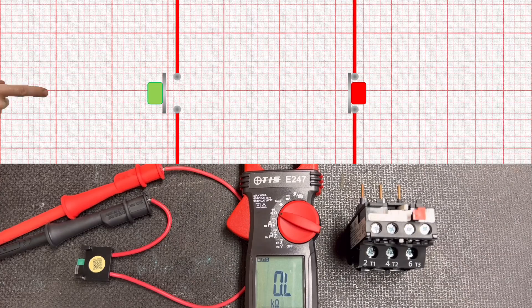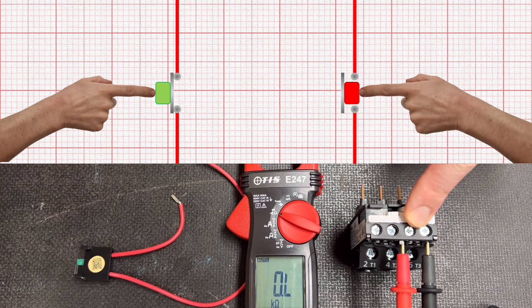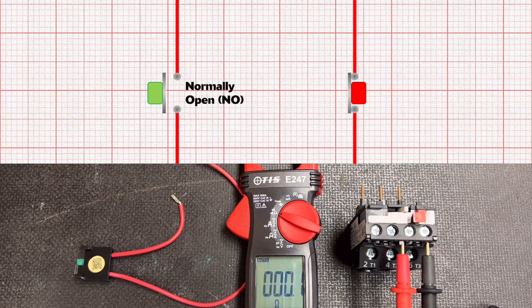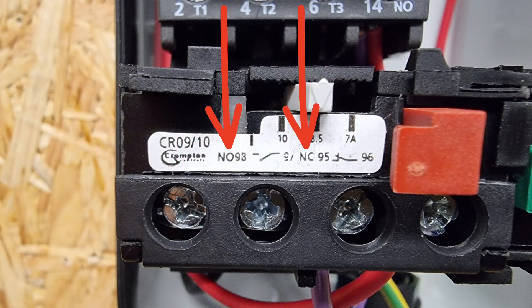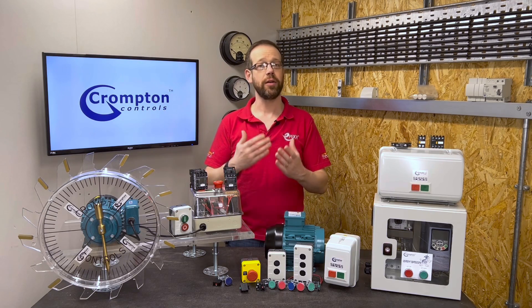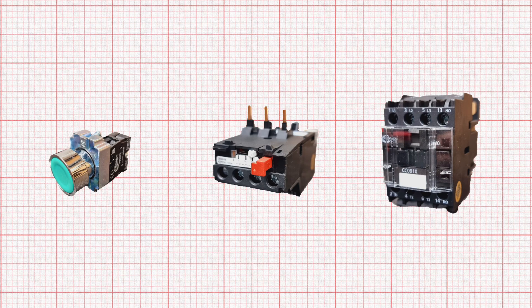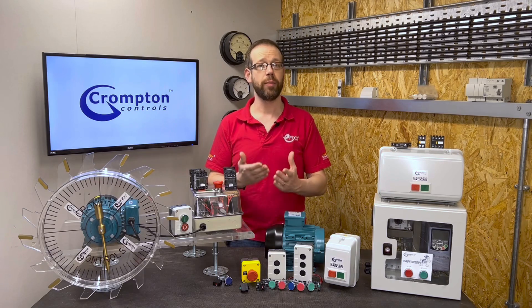This means the switches can be broken down into two different types: one that makes a connection when you press it, and one that breaks a connection when you press it. We refer to these as normally open (NO) and normally closed (NC) — you may have seen those letters on the contactor and overload in the previous video. In this context, 'normal' means the state they're in when no external force is acting on them. So for a manually operated button, normal is when it's not being pressed. For a contact on an overload relay, it means when it hasn't tripped due to a fault. For a contactor, normal is when the contactor is not energised. So for our control buttons, the start button will usually be a normally open contact.